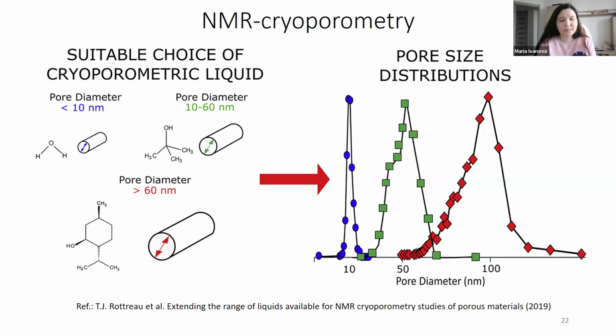Another type of NMR experiment for estimation of the pore size distribution is NMR cryoporometry. Here, in addition to the benchtop NMR analyzer, a variable temperature probe is required. So for this analysis, we use a special system which varies the temperature from, for example, 40 degrees to minus 60 degrees Celsius.